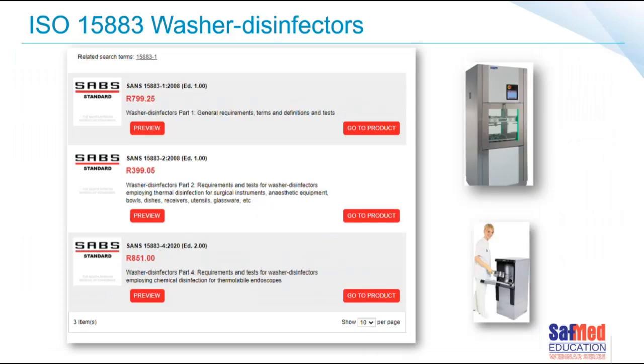You may say ISO is international — what about South Africa? South Africa has already adopted a number of the ISO 15883 guidelines. We have SANS 15883 part one, we've adopted part two for washer disinfectors, we've adopted part four for endoscopes, and we are in the process of adopting part three for bedpan washers.